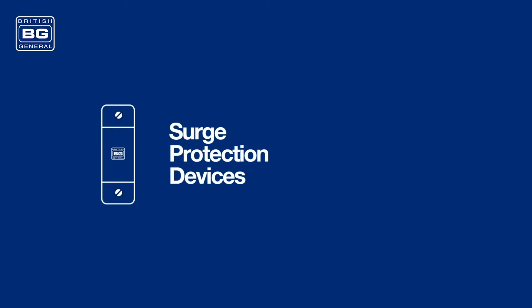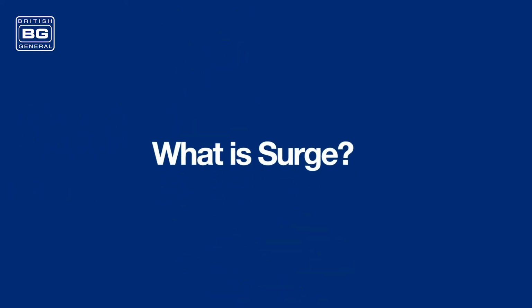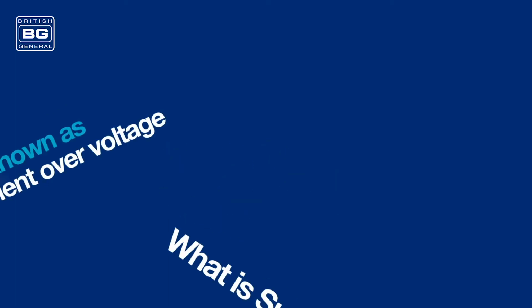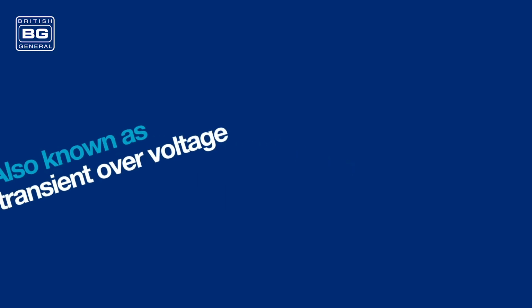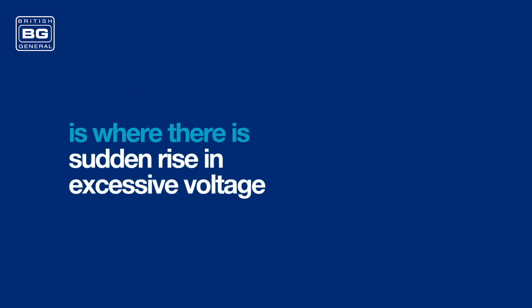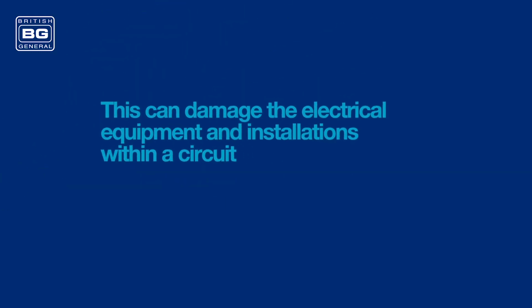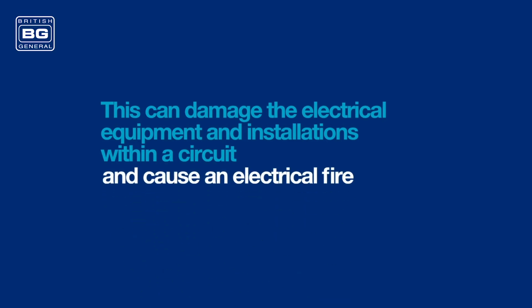With the rollout of the 18th edition of wiring regulations, surge protection plays a major role in this latest update. But first, what is surge? Surge, also known as transient overvoltage, is when there is a sudden rise in excessive voltage. This can damage the electrical equipment and installations within a circuit and cause an electrical fire.